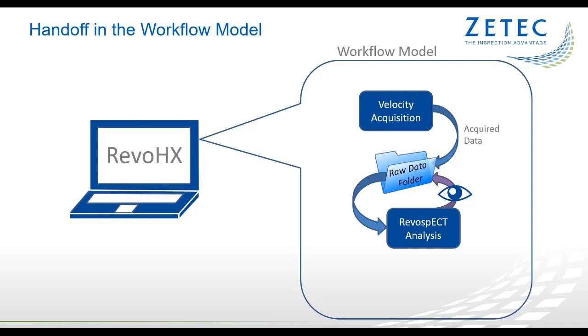At the end of the acquisition sequence, when the probe exits the tube and the recording of data stops, a file is created and dropped into a defined raw data file folder. This is on the hard drive within the RevoHX system. The Revo engine that is already running and watching for the arrival of the new data will start the analysis process once this data file is submitted into the processing engine for the analysis, along with instructions on the analysis process, which we call the configuration. Output of this analysis is reported into a database to be ready for final reporting and review.